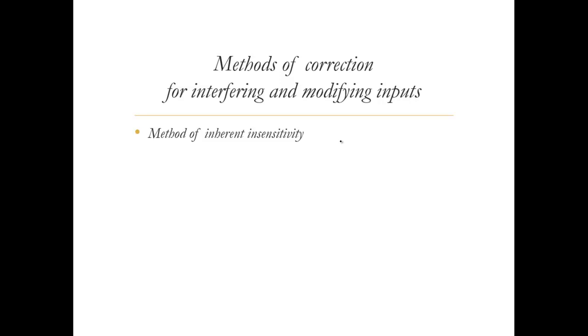So even if the temperature changes, it really doesn't matter in the change in the resistance of the specimen of the instrument. That is something called the method of inherent insensitivity, where you design the components in such a way that they are actually insensitive to these types of disturbance, or these types of interfering and modifying inputs.